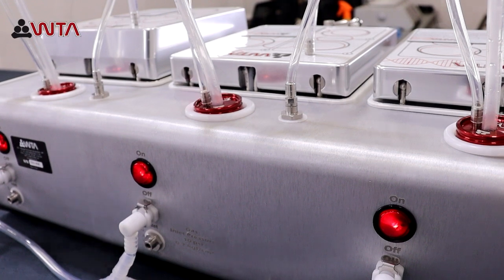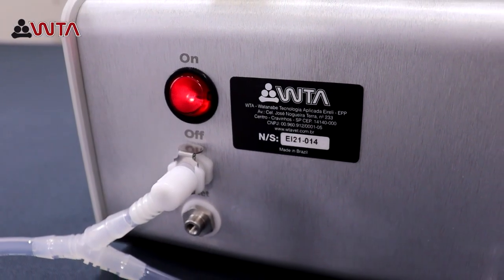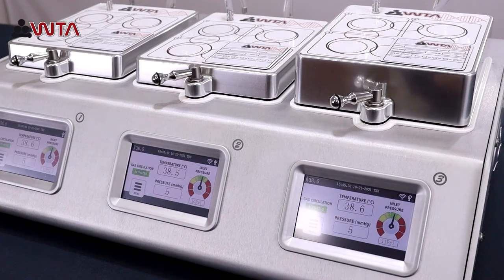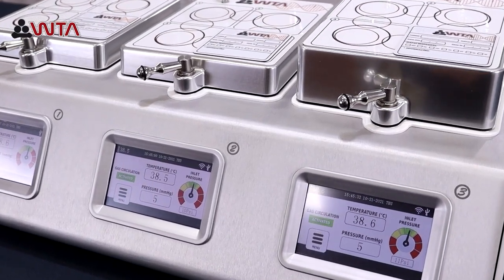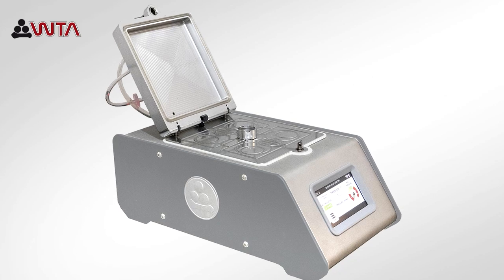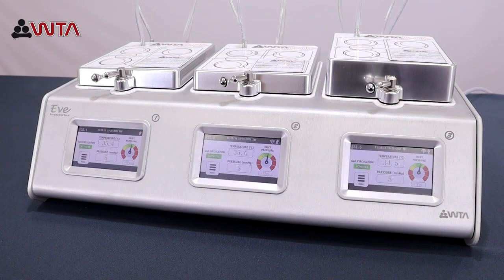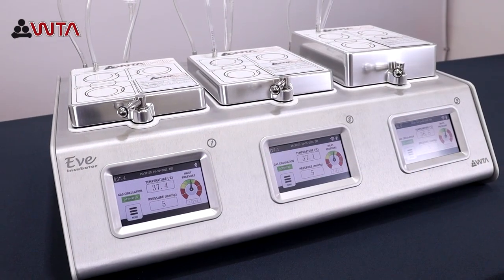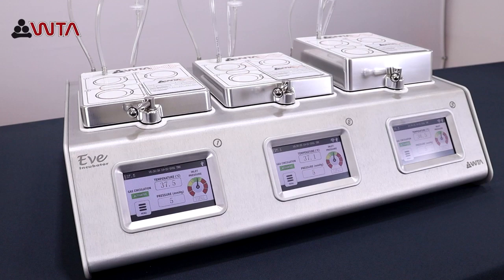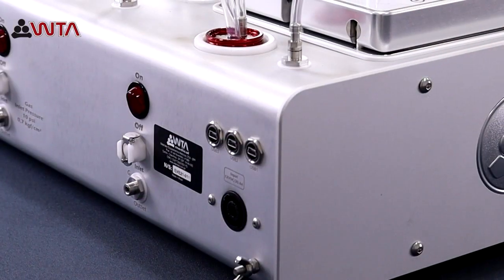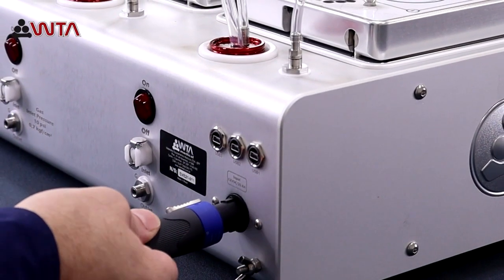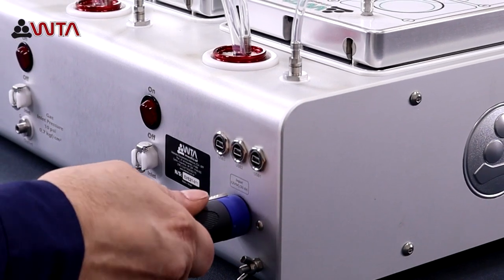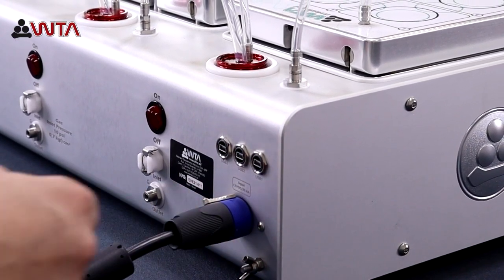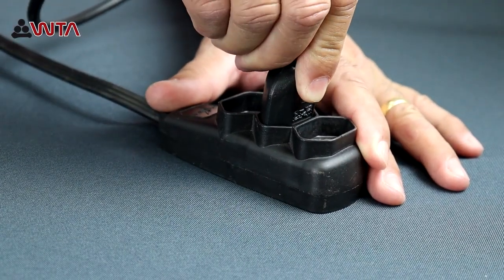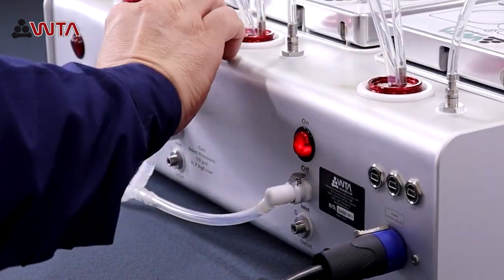First, let's connect the power supply. Plug the cable into the power supply connector on the back and turn it slightly until you hear it lock. Then plug the cable into your power source. As soon as the equipment is connected to power, press the on-off buttons. The buttons light up to indicate power is being received, and, in a few seconds, the front display will show the home screen we call 1. At this point, the incubator will be ready to be configured to the correct settings.